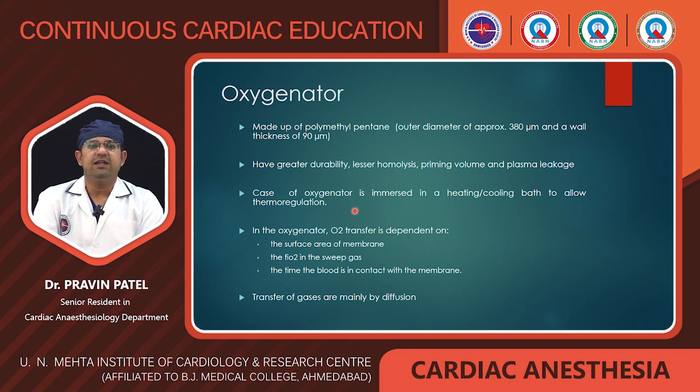The case of the oxygenator is immersed in a heating or cooling bath to allow thermoregulation. As I told, nowadays oxygenators are present with the integral part of the heat exchanger. O2 transfer is dependent upon the surface area of the membrane. If the surface area is large, the transfer is efficient. If the FiO2 of the sweep gas is higher, the oxygen transfer is also efficient. And the more the blood is in contact with the hollow fibers, the more efficient the oxygen transfer is.